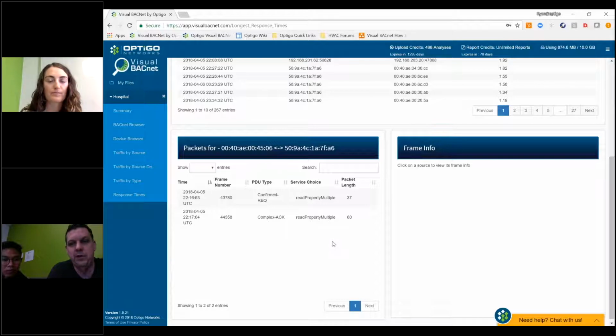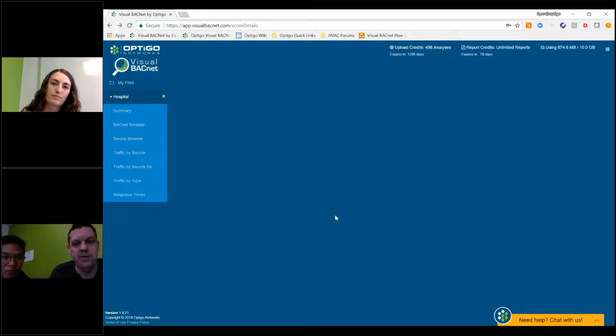You can put it from the server to the end device, you can put it from controller to controller, and it'll show up here, and we can just figure it out. At least you could eliminate it. Very common in lighting. Right, I push the switch and I wait 5 seconds for the lights to turn on. So it's an extra trick you can use to figure out some additional issues. And I think that's the end of this file.